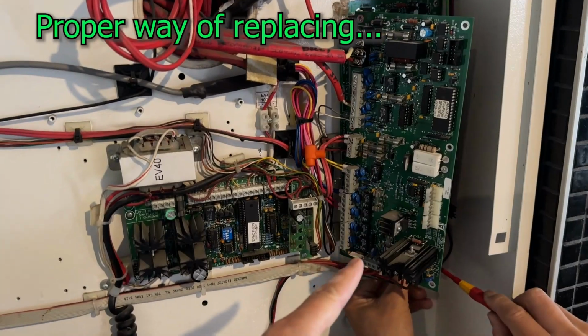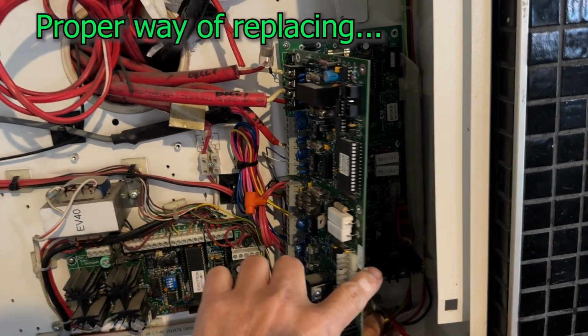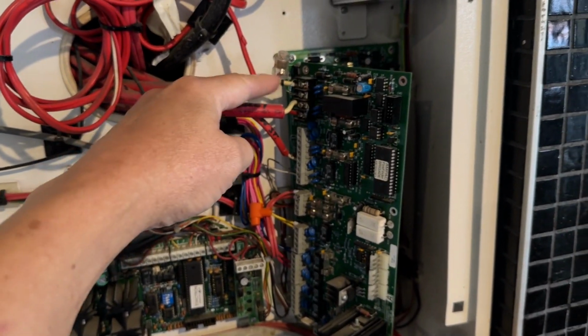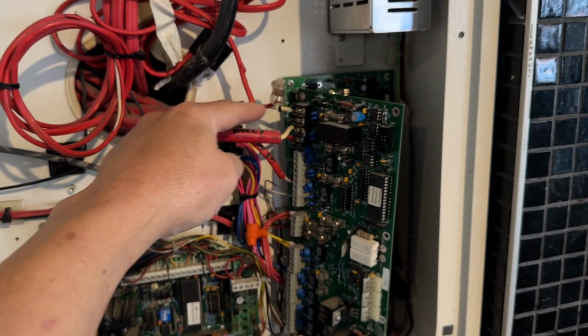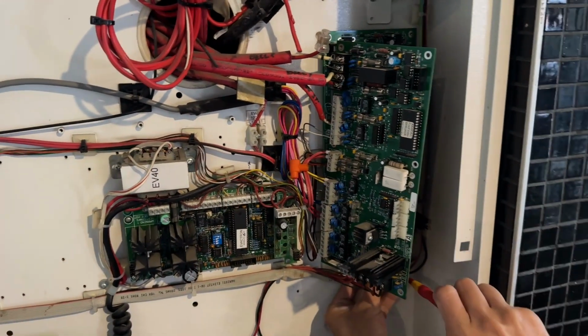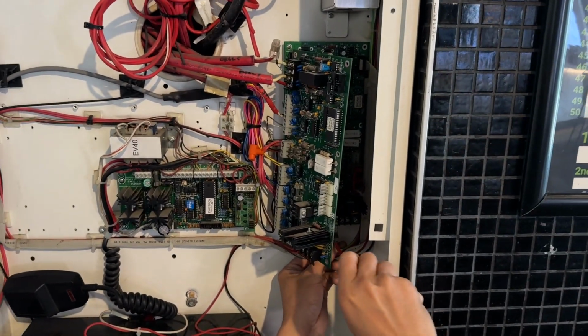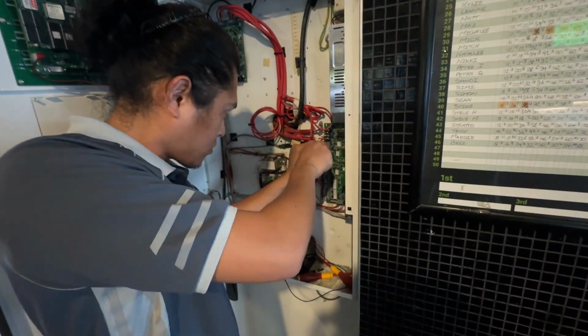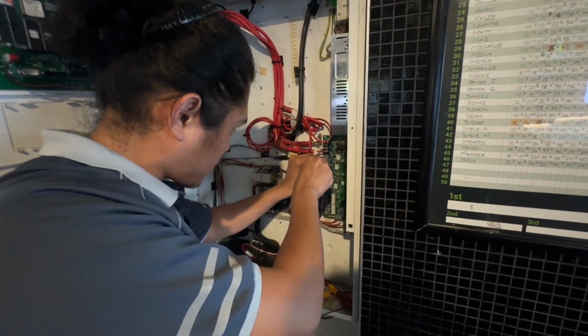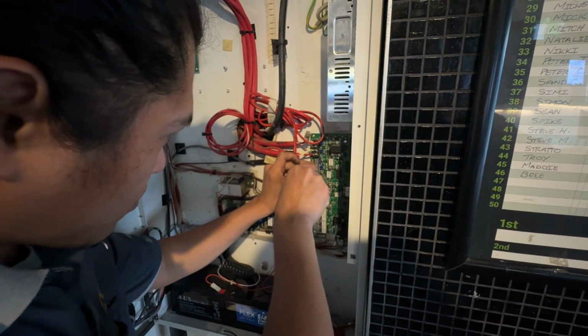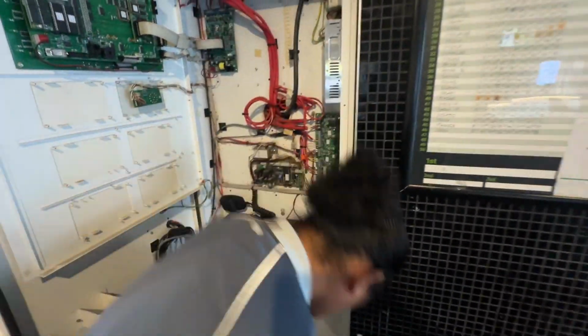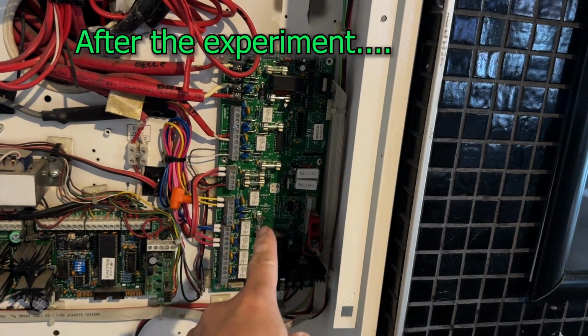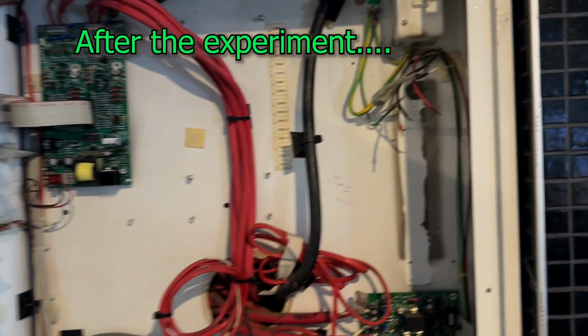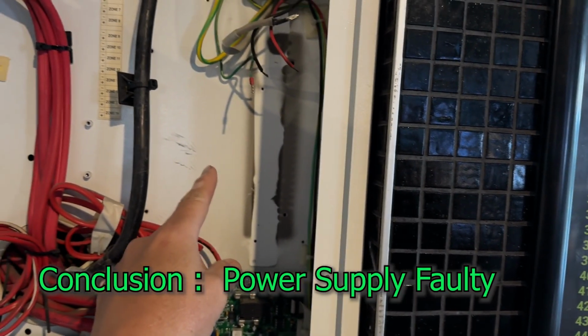So what we're doing now is replacing the brigade card, one at a time. That is the old card. That is the new card. So one by one, slowly we are transferring all those cables, so we don't mix up. The final touch, moving the resistor from the old card to the spare card, and that's it. And after that, we're going to switch it on. We rebooted the system, and we found out that we still have the same problem. So we're going to replace the power supply, and if that fails again, our problem is the main board.